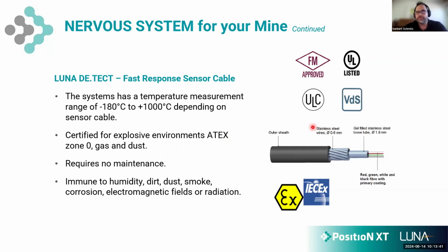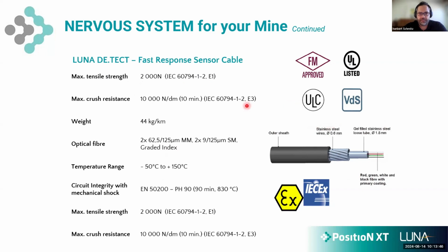And we'll share a bit more information on the testing we've done during the years as well. As I said, 2 single mode and 2 multi-mode cores, depending on the distances we want to measure. These cables are fully fire survival rated, PH 90 rated. And this allows us to also communicate emergency signals through this fiber optic cable. It is approved for that application as well.